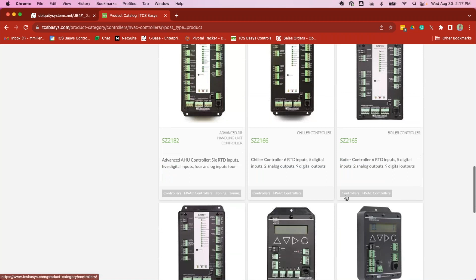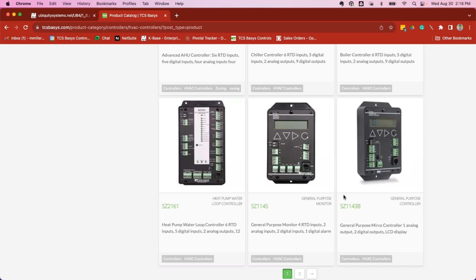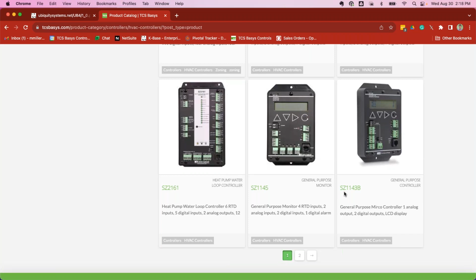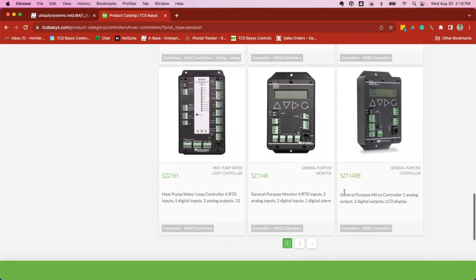We incorporate loop controllers, so if you end up having a geothermal system or a water source heat pump system, you have a primary condenser loop which will end up heating and cooling that loop in order to maintain those heat pumps. Then we have general purpose controllers, but these are all configurable controllers, so they can be activated by starting and stopping them directly, simply by addressing and powering them. Alternately, we have a free software, Insight, that lets you configure those controllers before you even get them powered up.